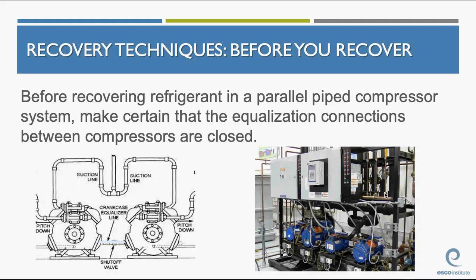Before recovering refrigerant in a parallel pipe compressor, make sure that the equalization connections between the compressors are closed. Okay, guys, this is something we really haven't talked about. This is a supermarket rack system. Those of you in York have definitely seen this before because you have one in your shop. Okay? For everybody else and for the guys in York who haven't looked closely at that system that you have in your shop, between every compressor in the rack system, there's an equalization line. Okay, I've just drawn a light blue highlight on where it's at.